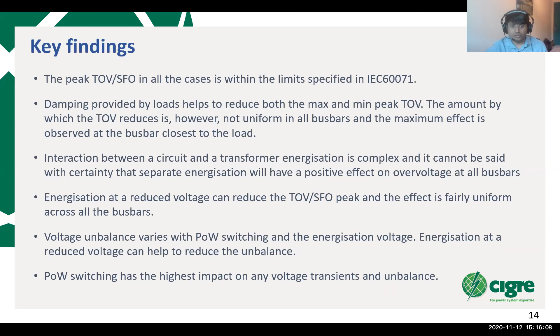For voltage unbalance, we found that point on wave switching and energization voltage both have a positive impact, and it can help reduce the unbalance in the network, especially when energizing network components like this 132 kV unbalanced line. Looking at all these case studies, not just the ones presented here but in our July 20 PET report, point on wave switching has the highest impact, be it on voltage transients or unbalance. So if a case study shows a particular problem with voltage transients, point on wave switching could be a good option, or for that particular restoration sequence we might need to use such an intervention technique. So with that, thanks a lot for listening to my presentation.